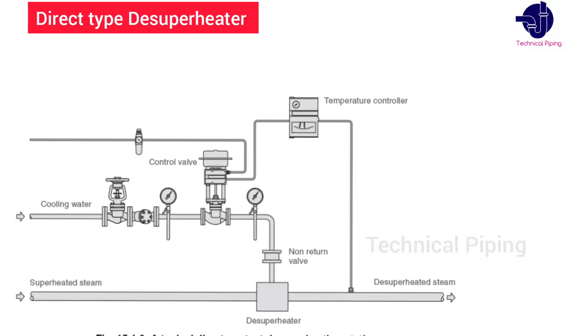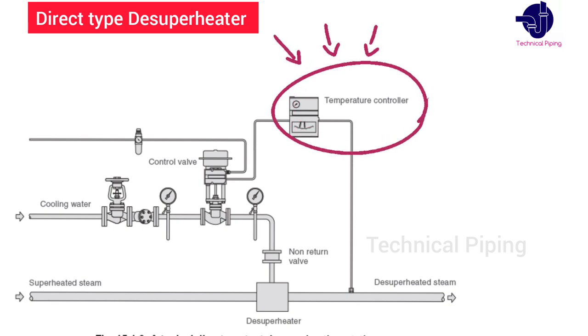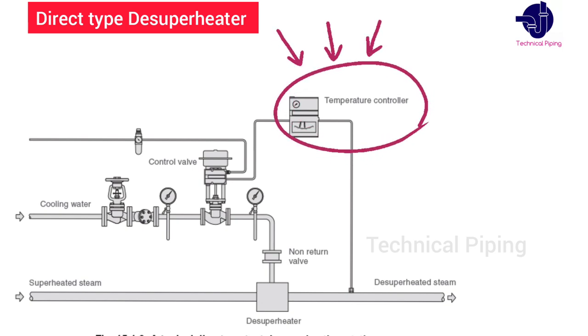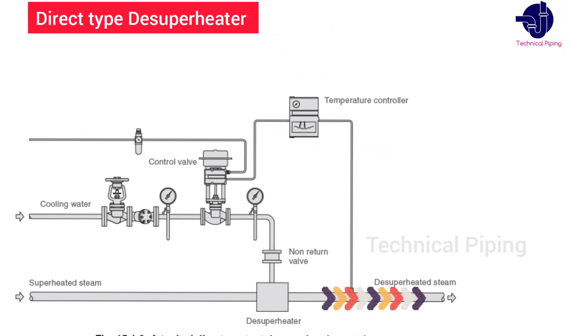The amount of water injected into the desuperheater is controlled by a valve, which is part of the temperature controller. The temperature controller reads the steam temperature downstream from the desuperheater to determine the valve position.